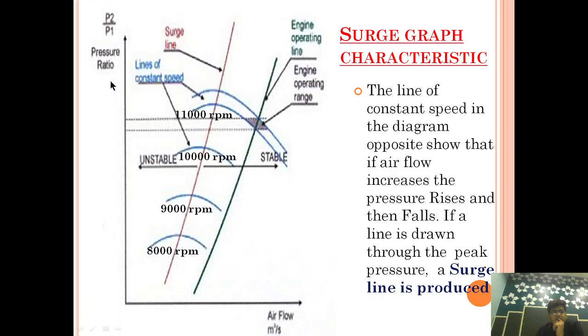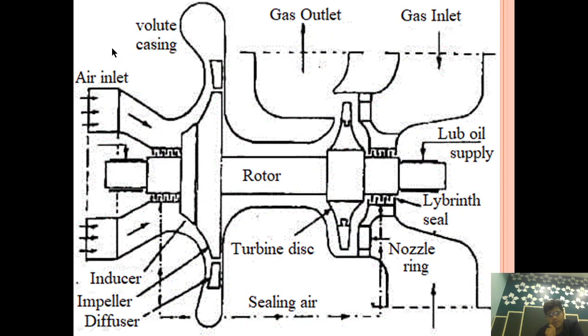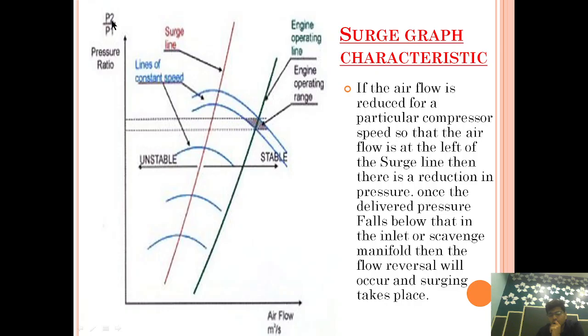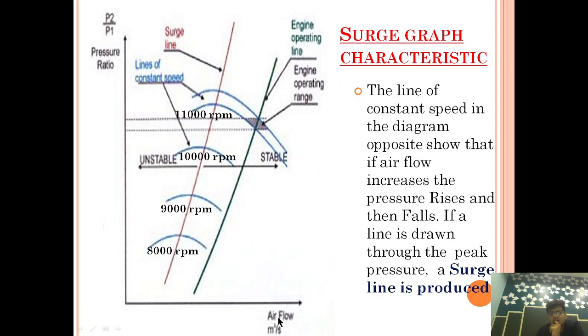First let's see what the axes are. On the y-axis we have pressure ratio P2 by P1, and on the x-axis we have airflow in meters per second. This pressure ratio P2 by P1 means: suppose air is entering at 1 bar and going out after passing through the diffuser and volute casing at 4 bar. The ratio of 4 by 1 is the pressure ratio. Now this is the airflow.